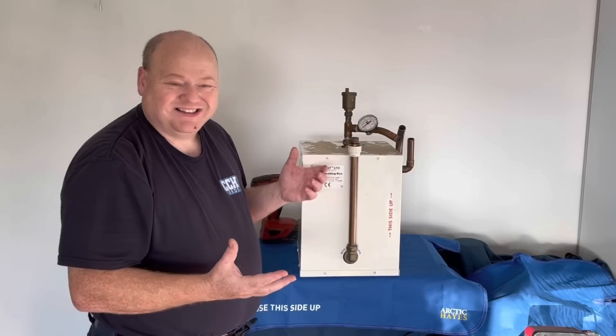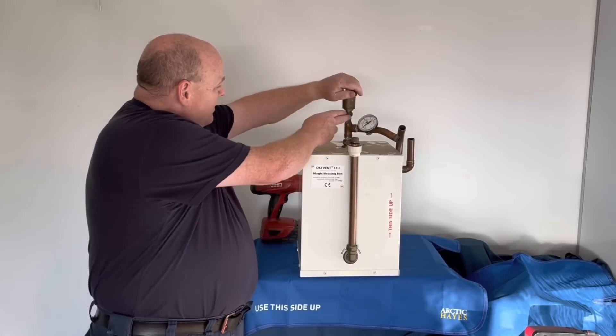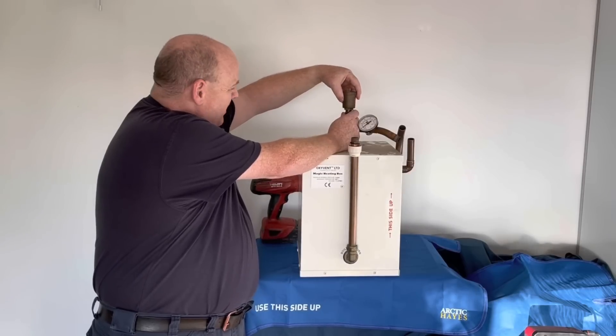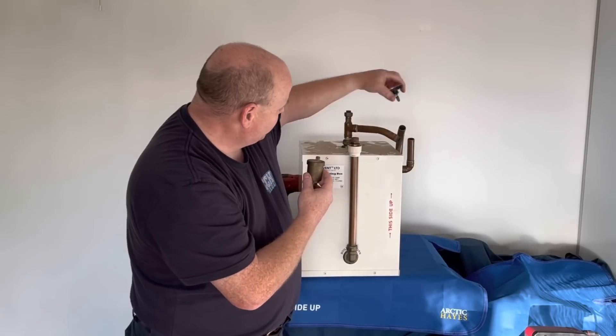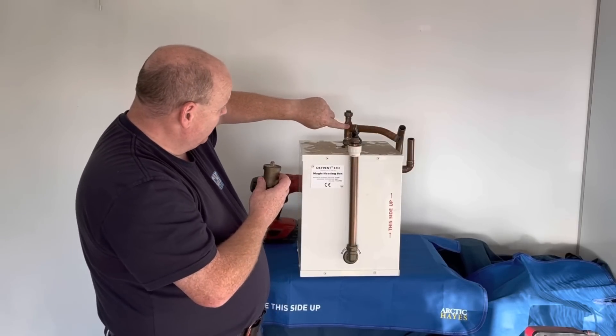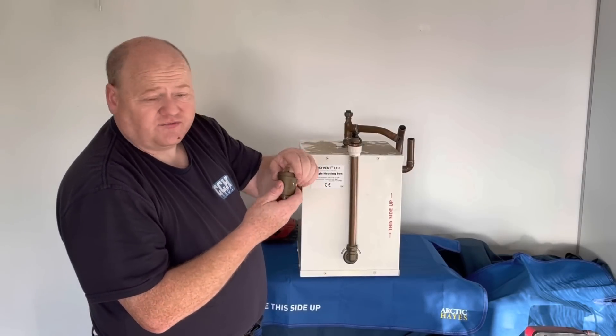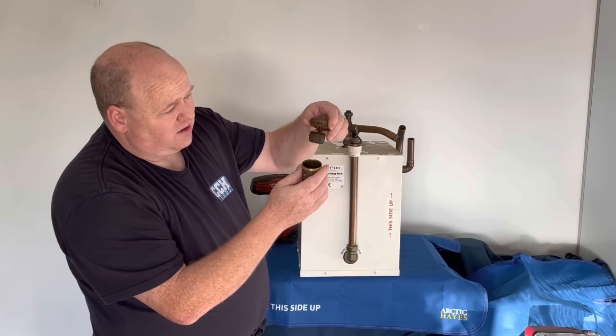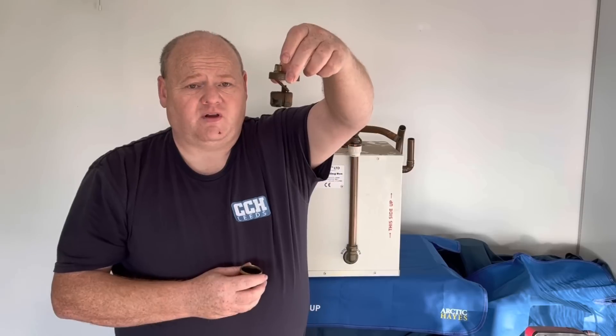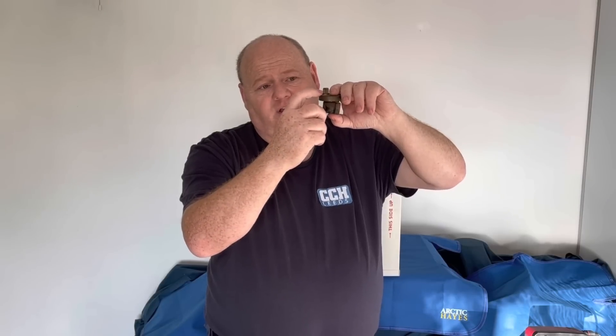So I'm going to have a look at the components. Starting at the top, we have an auto air vent - or that's what we think it is. I've just slackened this off to speed things up. We had this flow pipe from the boiler going into here, allowing air out through the auto air vent. How an air vent works: when there's air in here the float goes down, it opens the little pin, and allows the air to come out. As it fills up with water, that pushes up and closes the auto air vent.